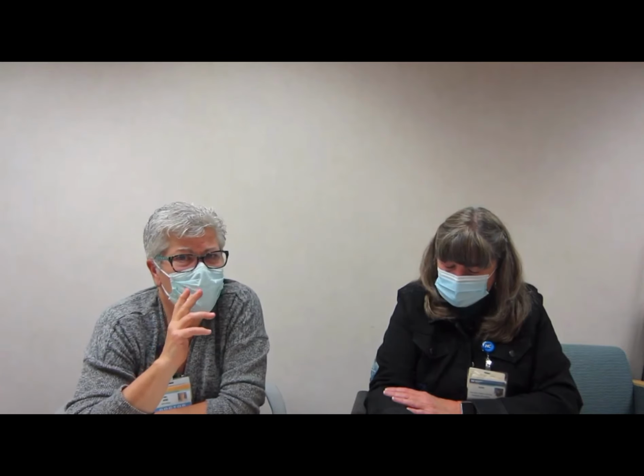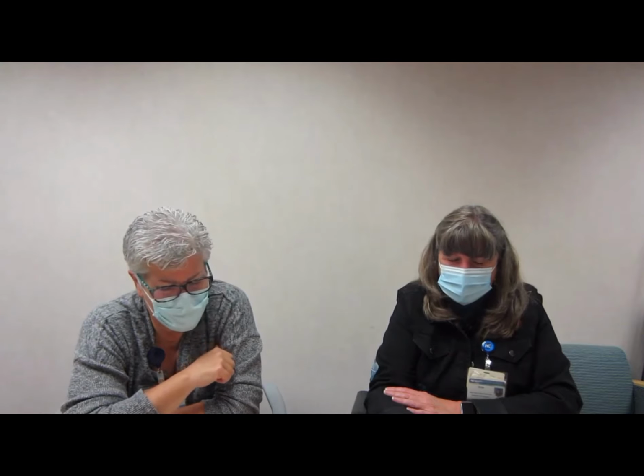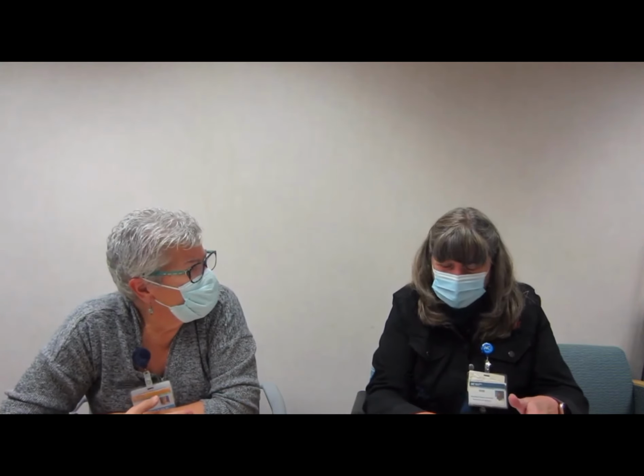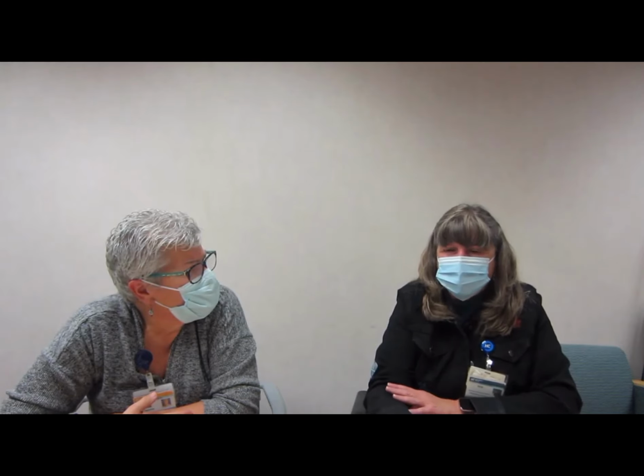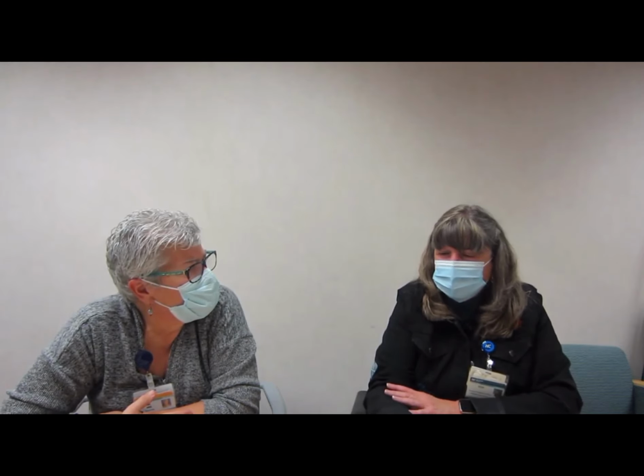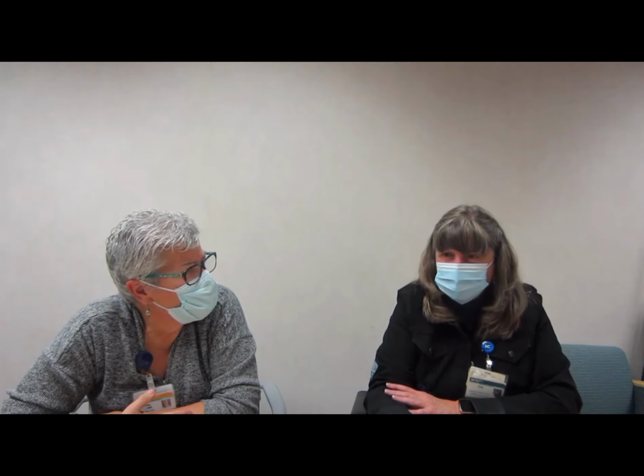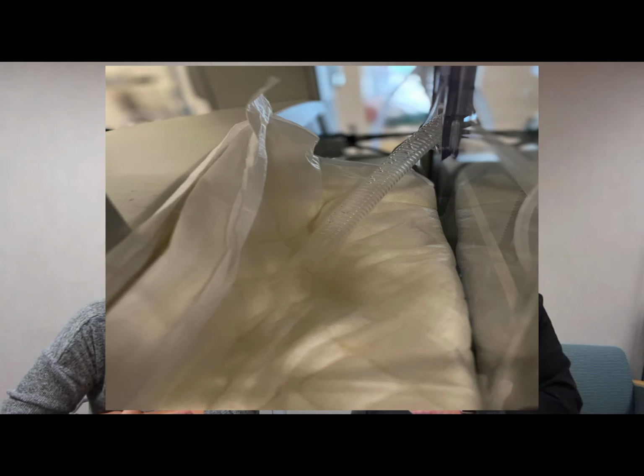Water in the tubing: we need humidity in those tubings to humidify the airway of the baby. It's very important. But too much water and the pooling of that water can really affect the mechanics of the ventilator or the CPAP, so you really have to keep your eye out for that. It's especially important in the jet because the water you see at the back end of it is going to eventually work its way and spray down into the baby. There have been many occasions where the nurse will say the baby has bradyed and they don't see why. Probably a good amount of those are the water spraying into the baby's lungs. So it's not acceptable to leave it there.